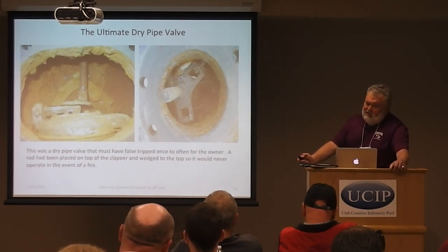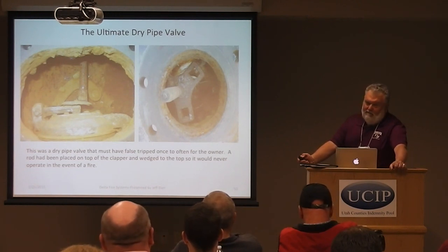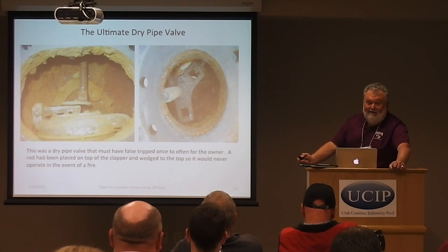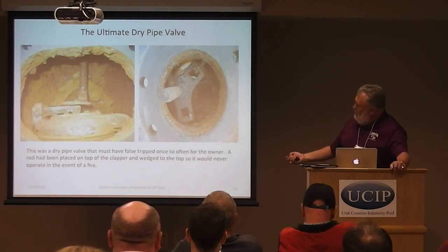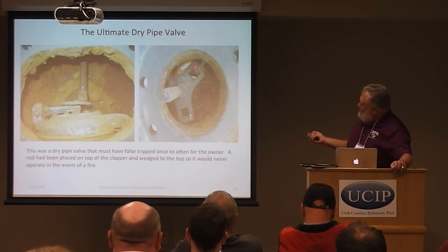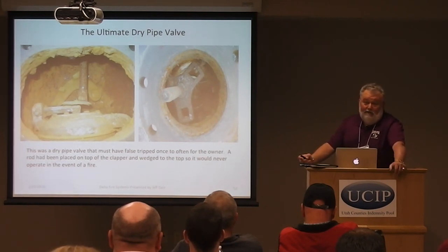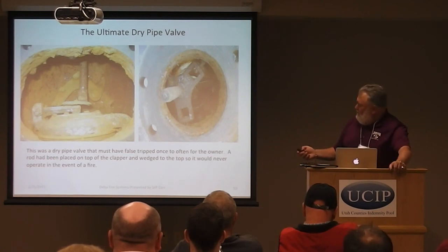Our 'ultimate dry pipe valve': we were called out by a trucking company that couldn't get their dry system to operate. We found that a maintenance guy, apparently tired of false trips, had fabricated a rod and plate with set screws that he set on top of the clapper inside the valve. If that valve tried to trip, the device would push up tight against the top of the valve body and prevent it from ever operating. We don't know how many years that system had the control valve wide open with everyone thinking they had a working system, but it would never have operated.